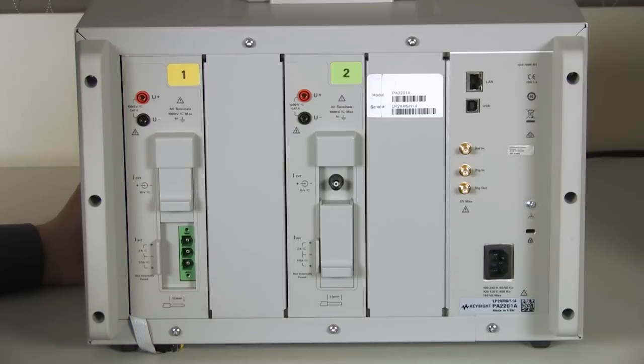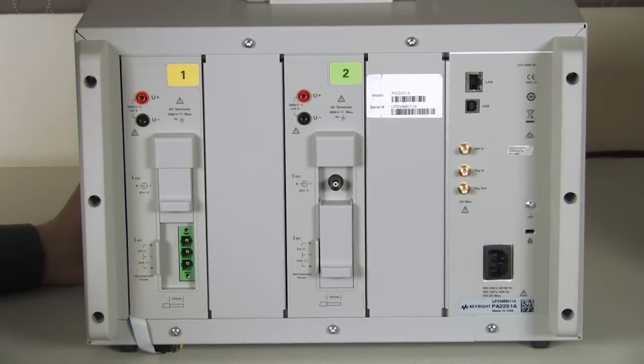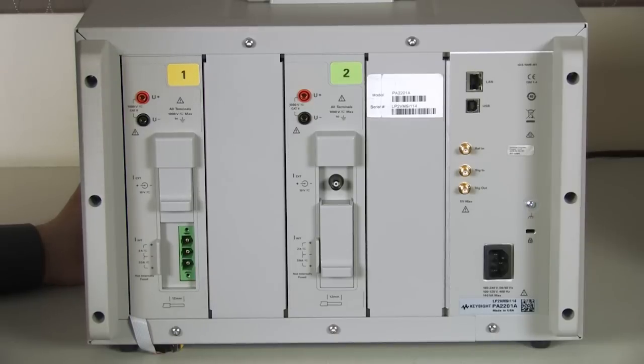With the LAN connection, you can actually use our remote front panel software to control the instrument from a distance. If you have some type of concerns around safety, around either the current or the voltages, you can physically be further away from the instrument and still have full control. So now let's move around to the front.